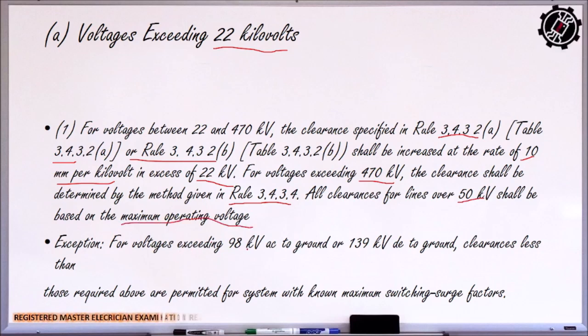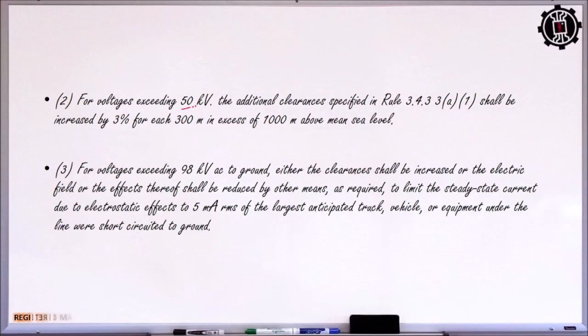So for voltages exceeding 98 kV AC to ground, so this is phase to ground na voltage for AC circuit, or 139 kV DC to ground, clearance less than those required above are permitted for system with known maximum switching surge factors. Okay, so for voltages exceeding 50 kV, the additional clearance specified on the table shall be increased by 3% for each 300 meters in excess of 1,000 meters above the mean sea level.